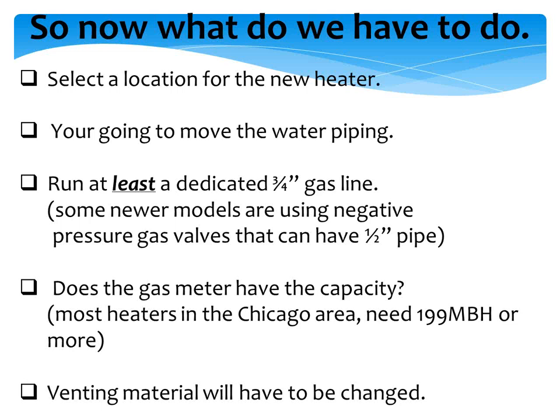Does the meter have the capacity? That's something that a lot of people don't think about. Here in the Chicago area, we're talking typically with our 40-degree incoming water, most water heaters are going to be 199,000 BTU, or you may end up with multiple heaters. Is the gas meter going to have the capacity? Typically, like a Chicago bungalow, I think most of the gas meters are only rated for about 285,000 BTU. So if we've got a 200,000 BTU water heater in there and a 125 or 150,000 BTU furnace, we're going to run out of gas. So do we have to get the gas company involved and get the meter changed?